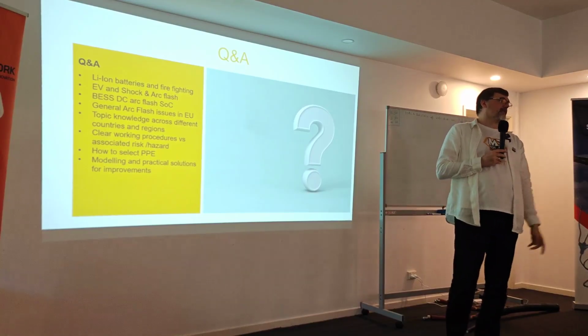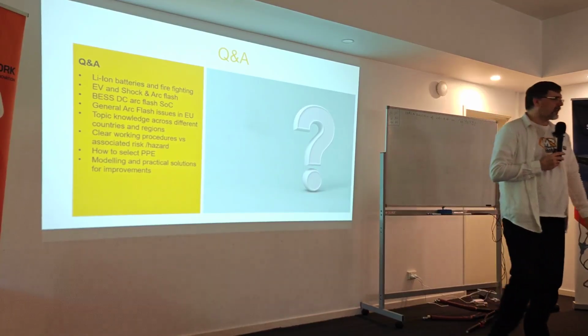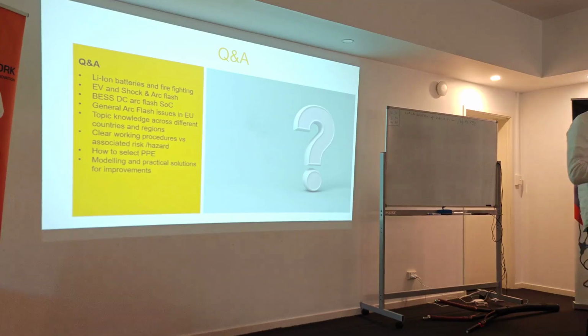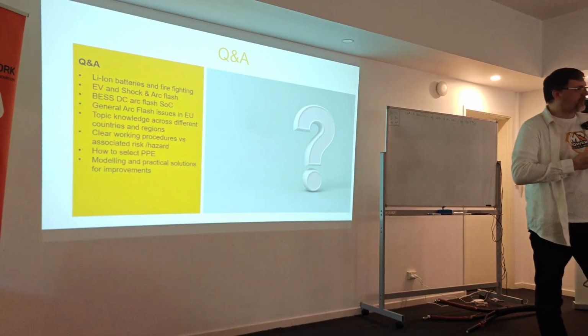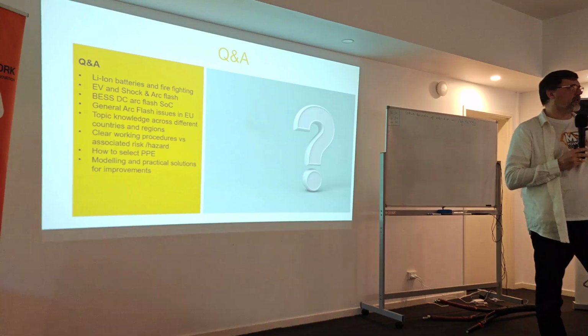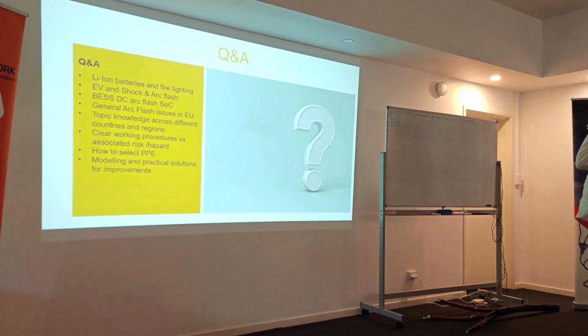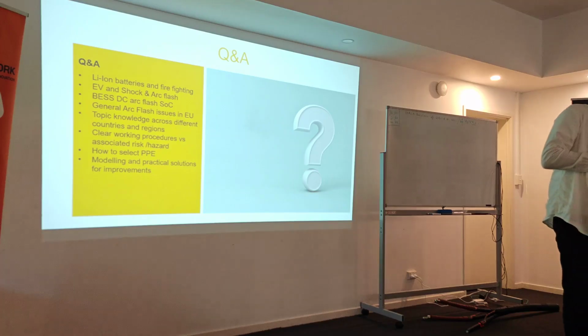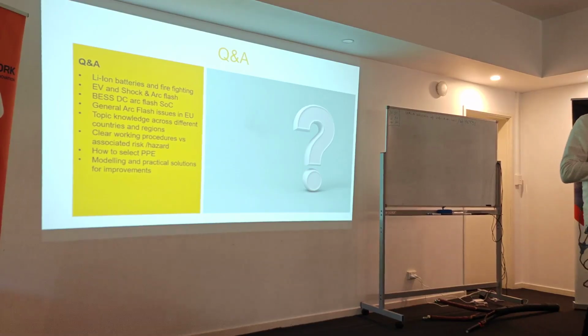And they actually made one stupid mistake, because I had to go back there after 1 month, because they told me that there was an accident. I said, how? Because we calculated it was almost impossible. But there was one step before, when they connected 2 batteries together. I think each battery was something like 48 volts. They connected 2 batteries together, and the battery has a plus-minus connection very close to each other. Normally the process was to open one, connect one, screw it, open the second one, connect the second one. But they removed both of them and just tried to connect, and they put the copper connection, and I think when the guy was screwing, they just made the short circuit, yeah?